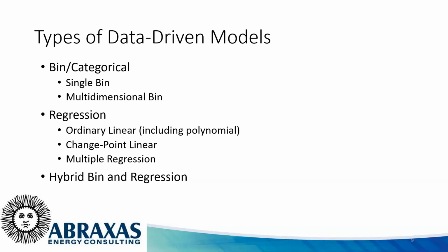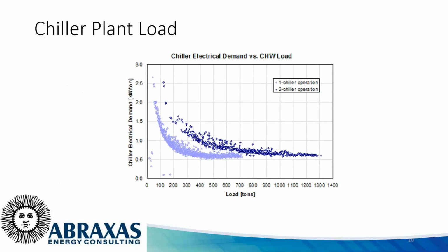Here's a first example of a problem I saw - this was a hotel many years ago. You see there are two clouds of data. Anytime there are two clouds of data, you want to think about segmenting your data. In this case, it's one chiller operation and two chiller operation. The obvious scenario here is the one chiller operation is the lower set of points, and you can tell on the upper set of points what a wide range of building loads.